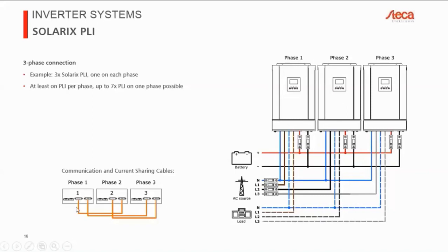You'll see here, there's no green cables. We have the communication cables, which we always require, so that we can do our phase shift between the 3 devices, again, and for parameters, etc. But the difference is, we have nothing connected to the current sharing cables now. And the reason is that now we have only one single inverter per phase. So there's no need for the inverter to share the load on a single phase with another inverter. But again, as soon as you're using more than one inverter on a single phase, you need to use these current sharing cables on that phase.